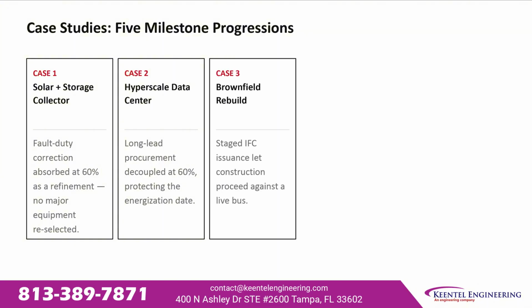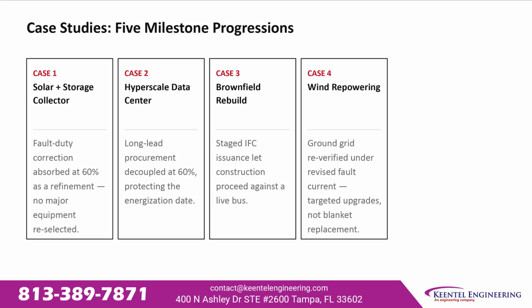The third is a brownfield rebuild with a live bus remaining in service. Staged IFC packages were issued by yard section, letting construction proceed zone by zone without halting the live bus. The fourth is a wind repowering project where the revised generation fleet changed fault current. Targeted grounding grid analysis identified which segments needed upgrading, avoiding blanket replacement of a grid that was largely still adequate.